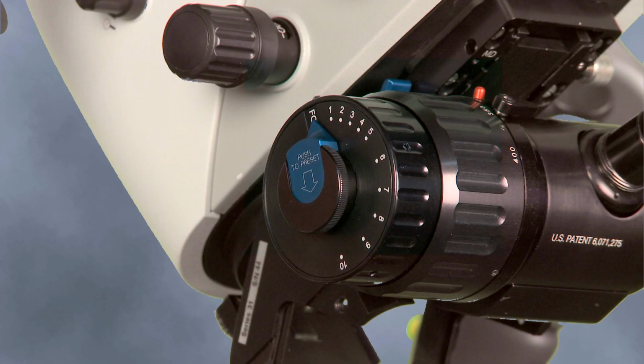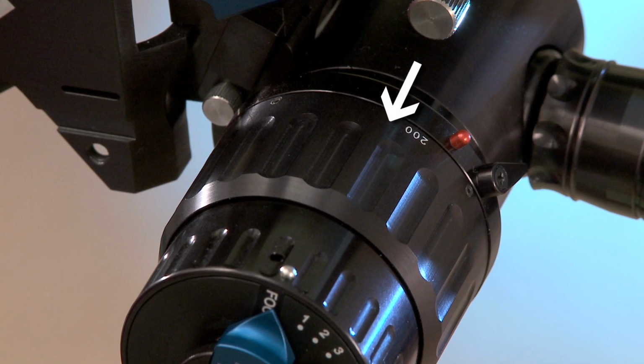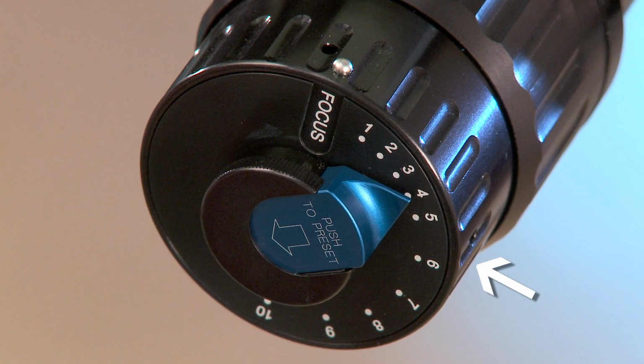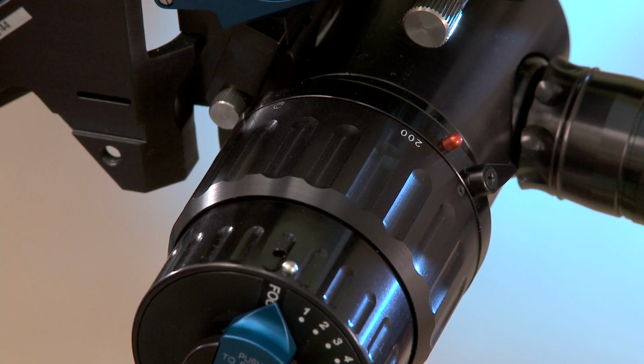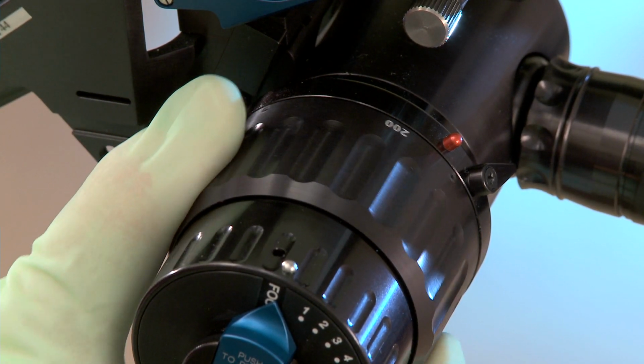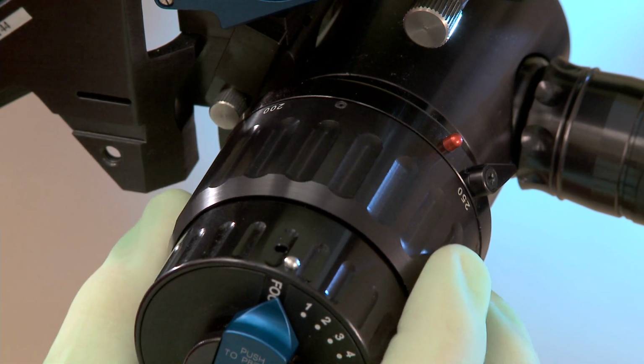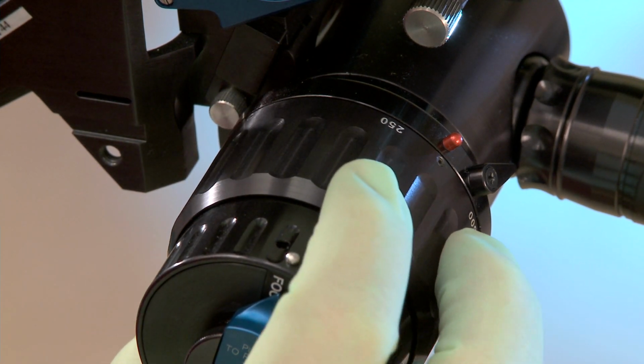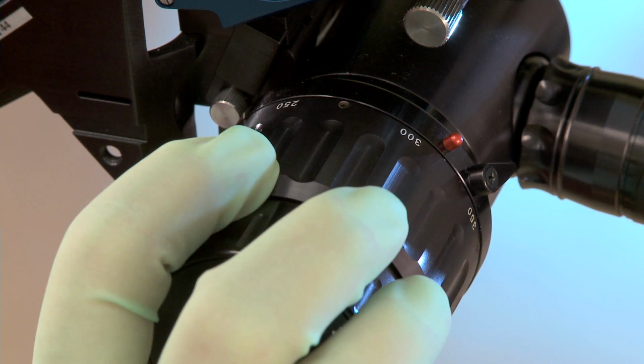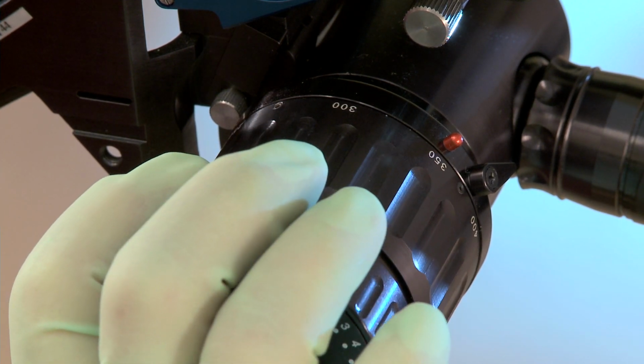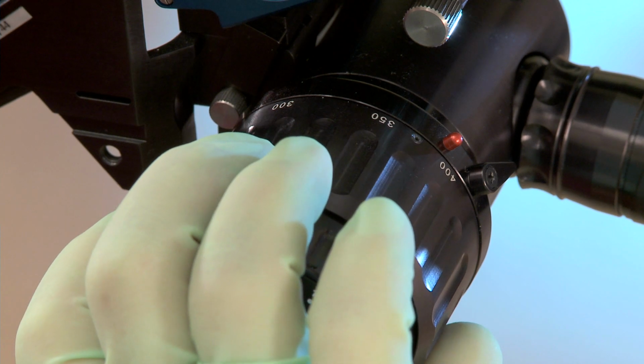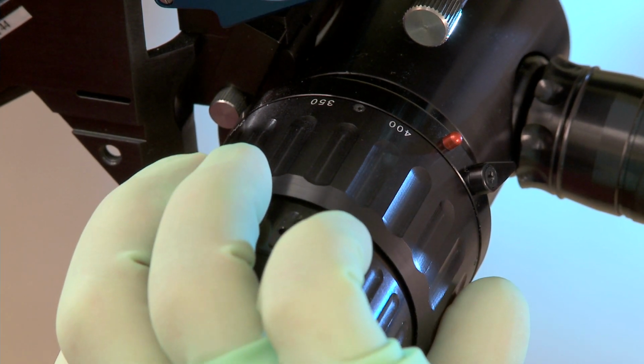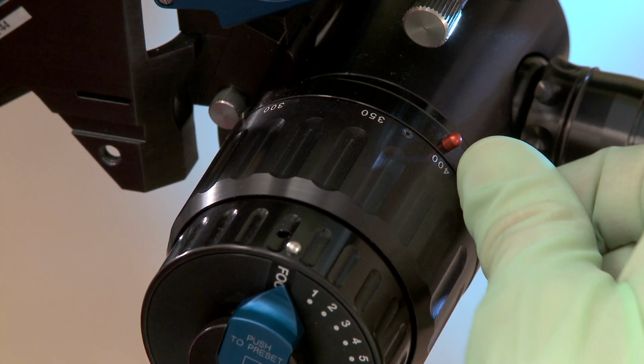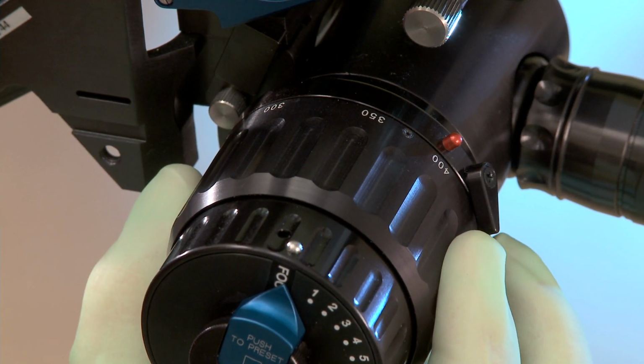The AccuSpot micromanipulator has a continuously variable defocus system with two main user controls, the working distance ring and the spot size knob. The working distance ring rotates continuously between 200 and 400 millimeters, so that the focus of the laser beam can be set to match that of the microscope. Depending on how far the micromanipulator mirror is situated in front of the microscope objective, the two working distance settings may differ slightly. The working distance ring has a lever which locks to prevent accidental movement.